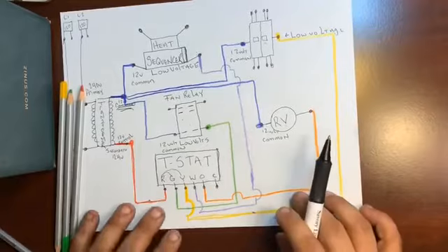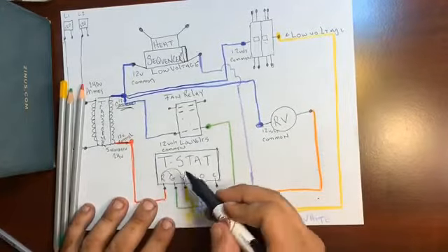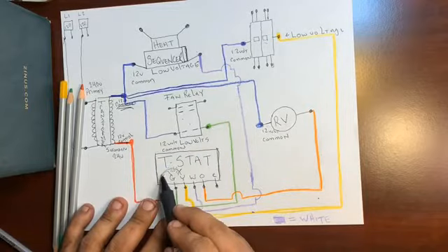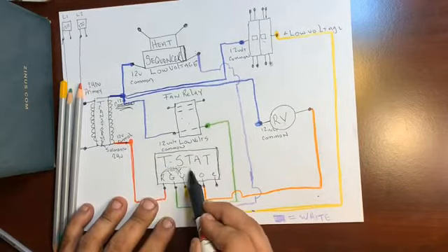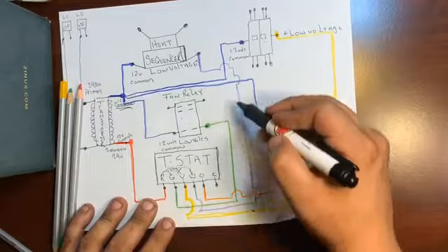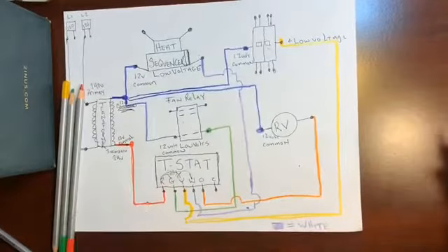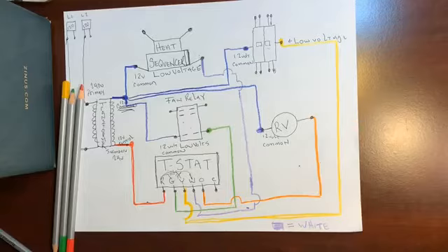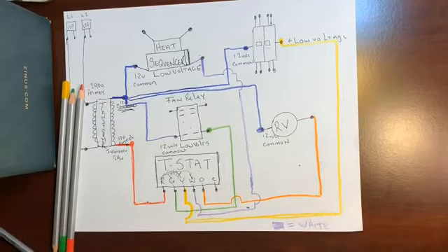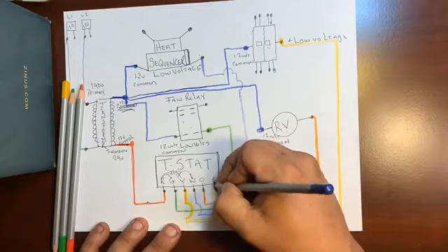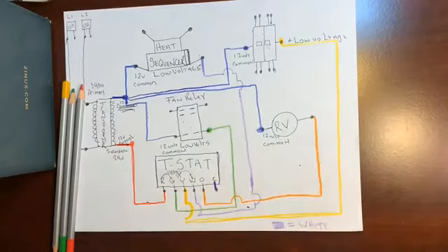Okay, wait, now we need heating. So when we need heating, we're not gonna use yellow anymore. We're still gonna use green, and the red is gonna use white because white is going to activate the heat sequencer and turn everything on. So that leaves us one last terminal on the thermostat, and the color is C. So if anyone can guess what the C means, it absolutely means common. Even the thermostat will get common.